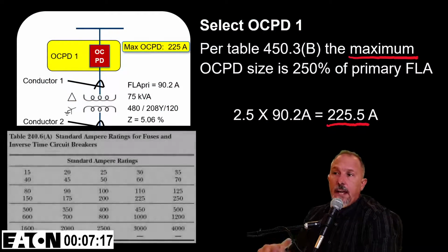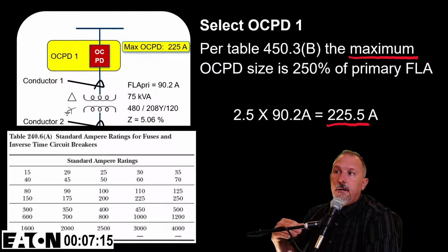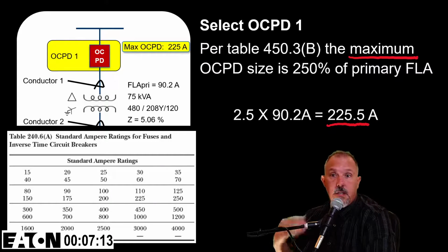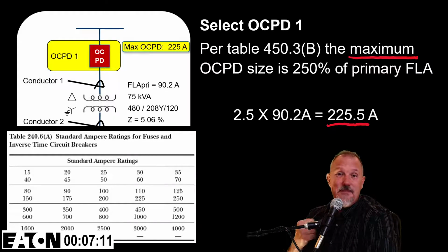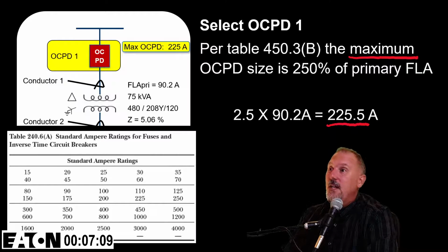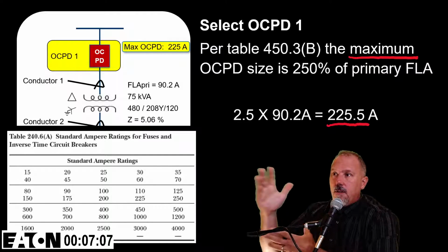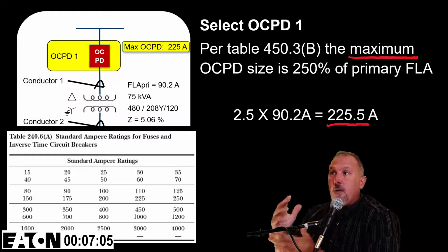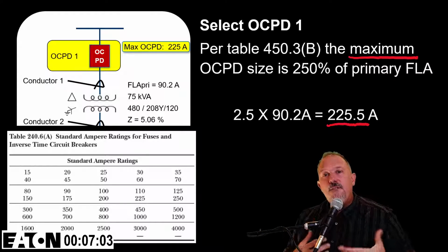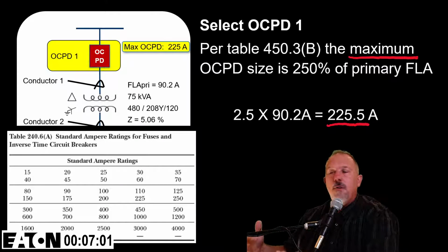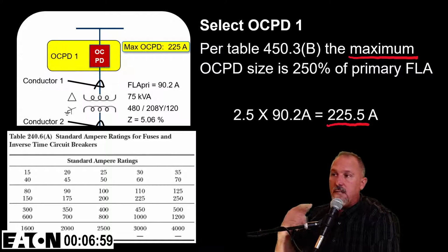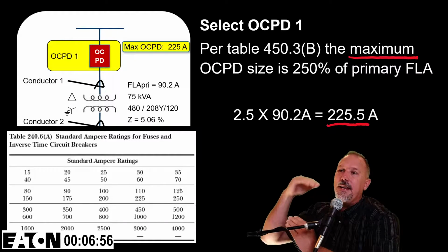Now, so if I look at selecting overcurrent protected device number 1, so that's the primary. I've still got 7 minutes to go. I'm doing pretty doggone good. So 225, if I take 90.2 and I multiply that by 2.5, I get 225.5 amps. I can't go, because I'm at 250%, I can't go to the next higher.